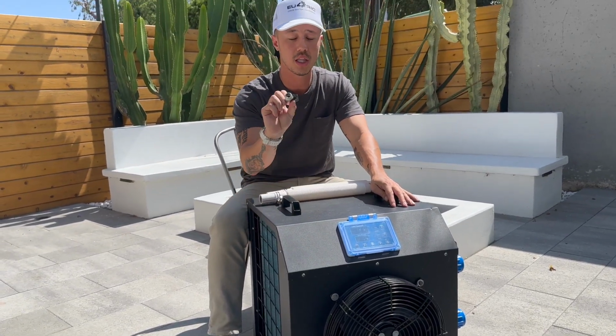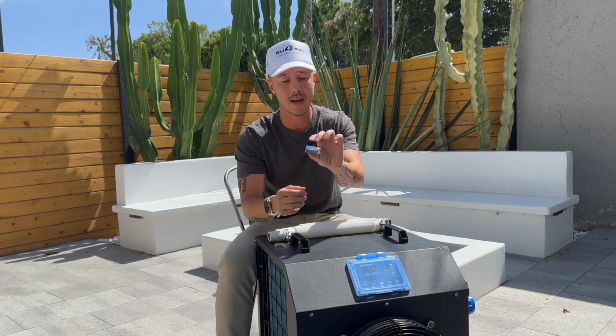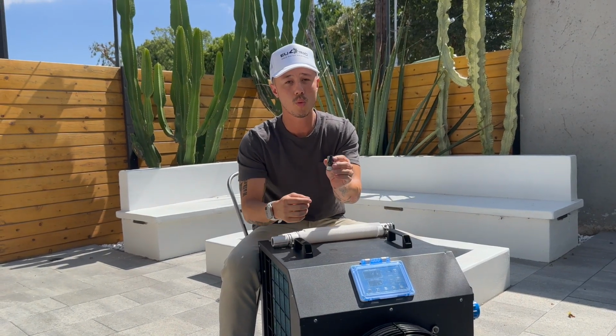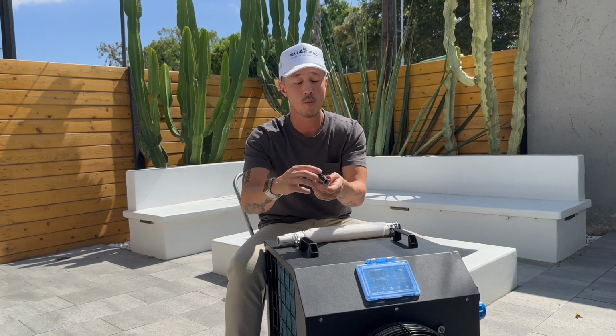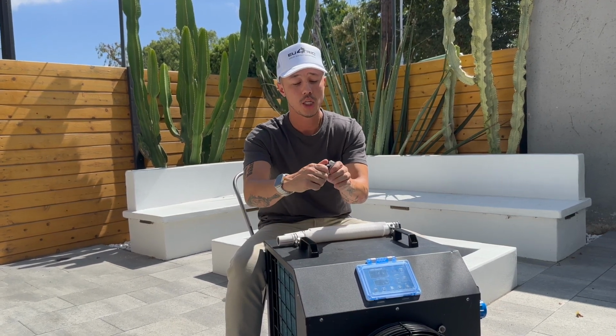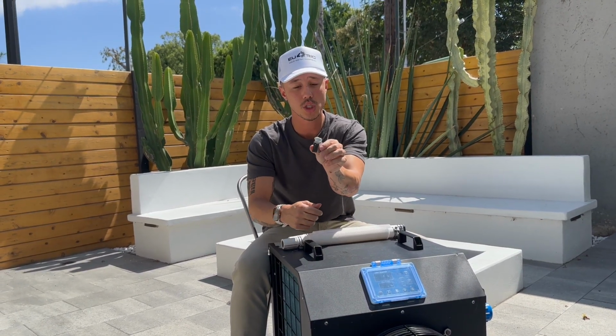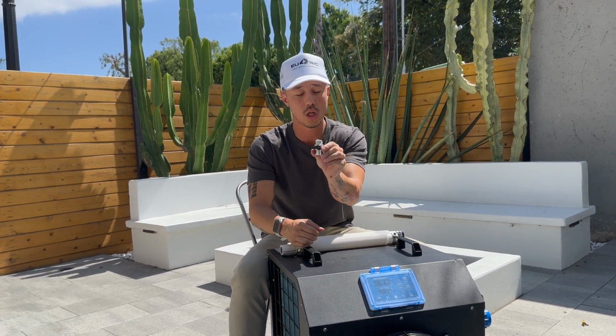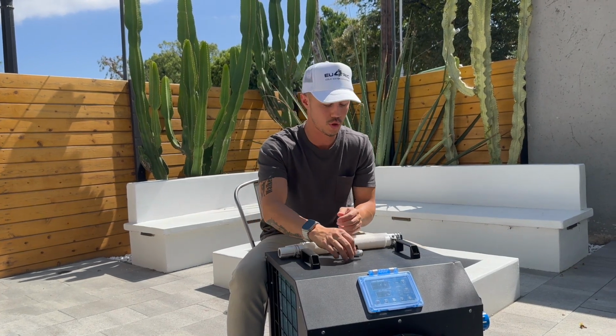It comes with a little valve inside the wheel bag. Remember, when you connect this, you should have two O-rings in here, and when you go to turn on your chiller, you want this valve like this, so it's on and not off. If you try to run the chiller while the valve is closed, you won't be able to pump any water through, and could actually damage your unit if you do it too long.